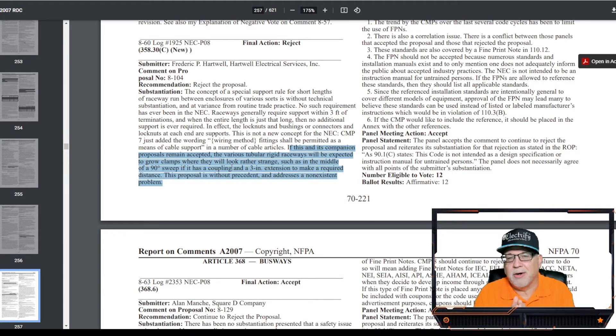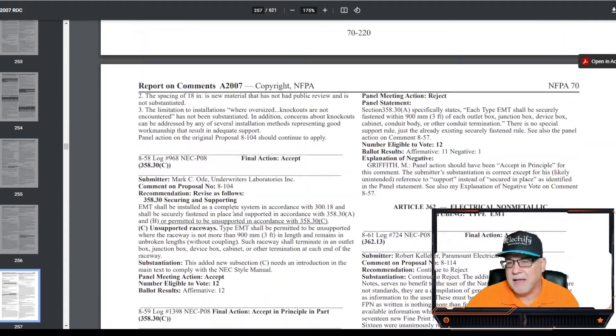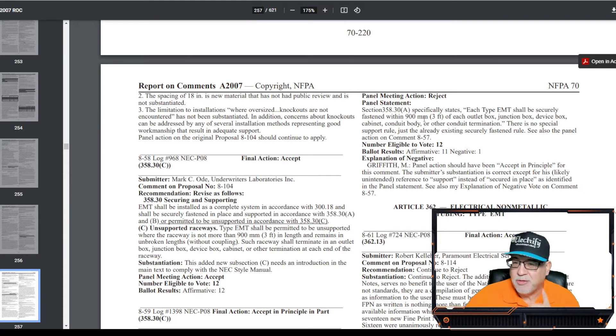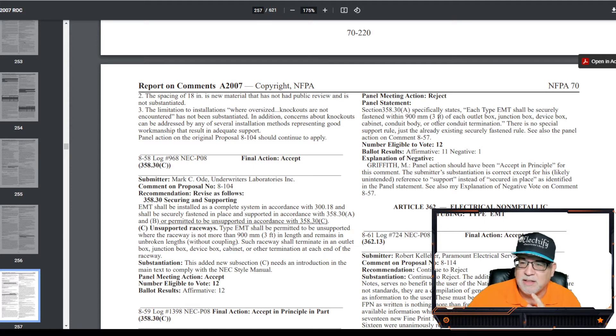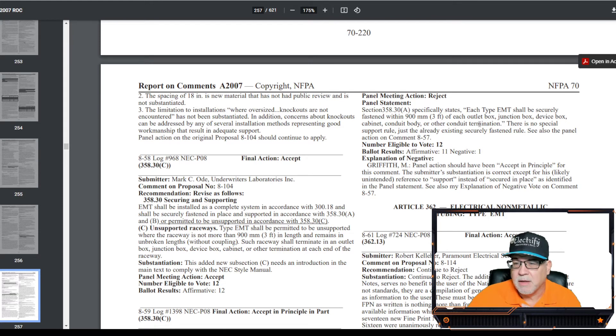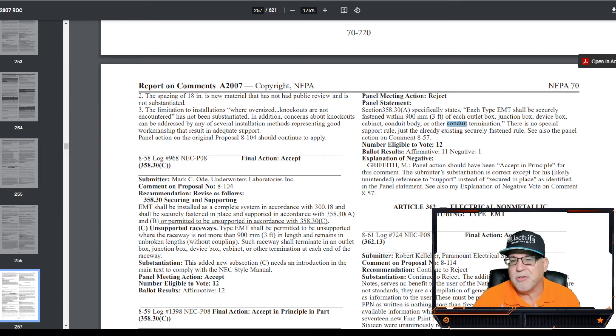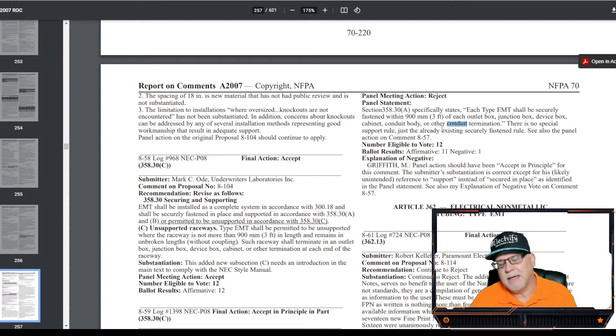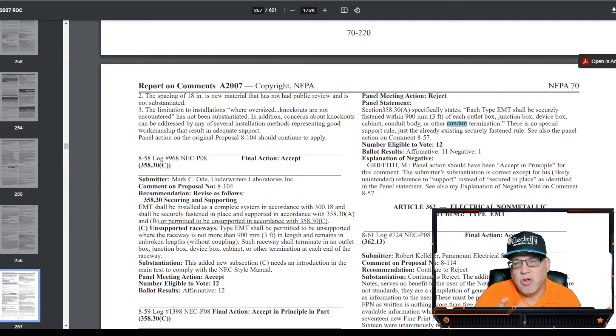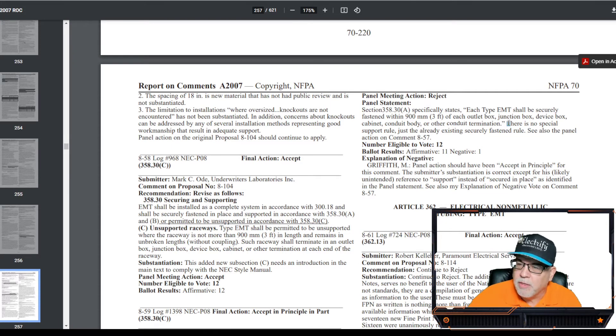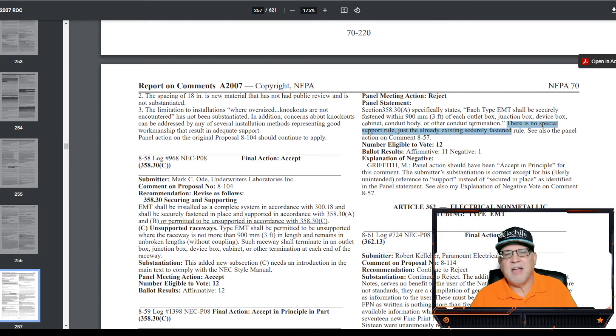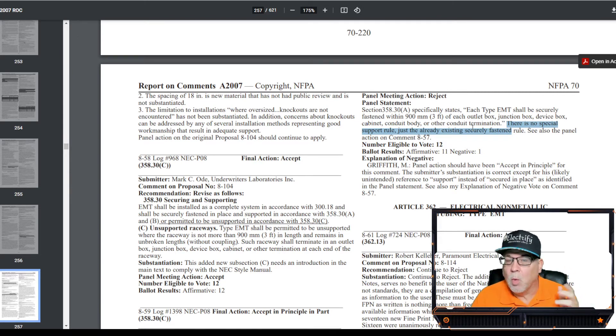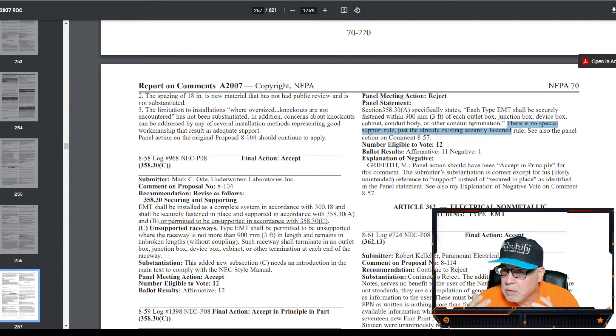Now, the code panel responded to that and said, Section 358.30 specifically states, each type of EMT shall be securely fastened within three feet of each outlet box, junction box, device box, cabinet, conduit body, or other conduit termination. In fact, they probably should re-evaluate their statement because EMT is not a conduit. It's a tubing, but that's okay. It happens. I get it. It should say, or other tubing terminations or other raceway terminations. Again, tubing is not a conduit, but it is a raceway. So anyway, it says, quote, there is no special support rule, just the already existing securely fastened rule. So what they're saying is, basically, the code stands on its own. We're going to add C. We really can't justify C, but we're going to accept C. You with me? So it ended up being printed in the 2008 edition of the National Electrical Code.